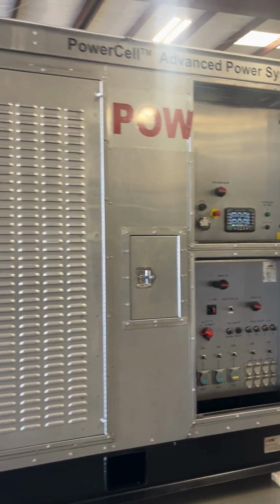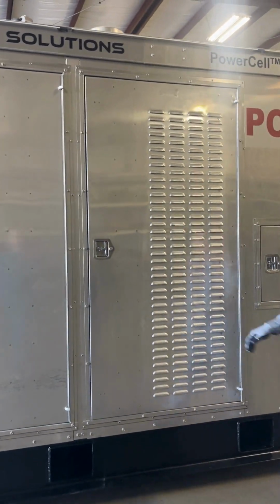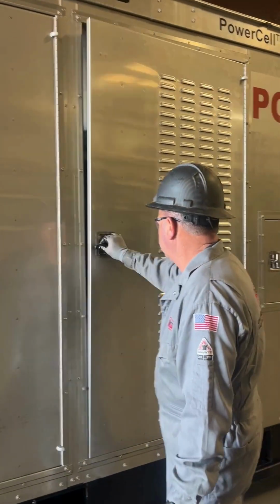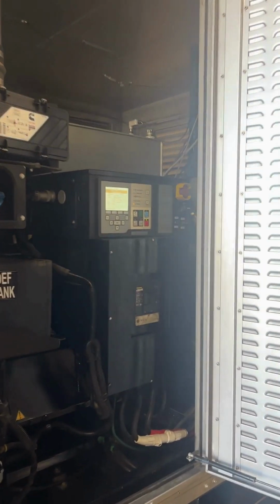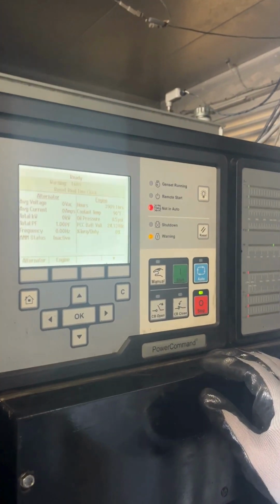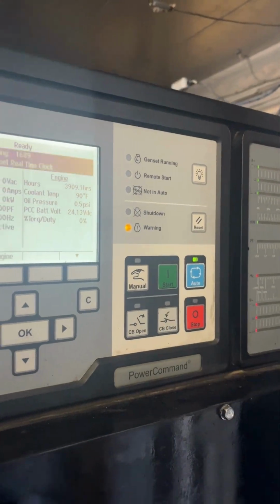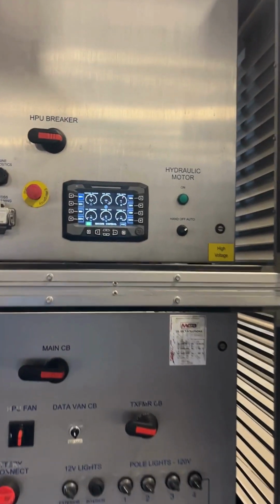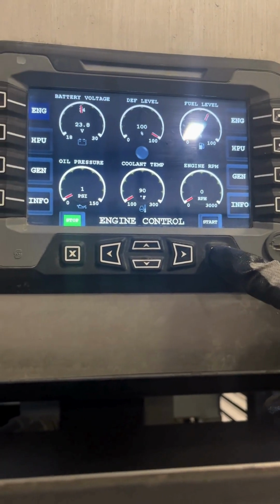So once we have verified all our switches are in the correct position and the computers have booted up, we go to the central door, which is at the generator's local control panel, and we want to make sure the master breaker is on, the local stop on the engine has not been activated, and we simply want to put the generator module in the auto position, which allows us to now use the remote control systems. We simply go back to the local panel or the remote panel. Make sure you're in the engine screen and simply hit start.